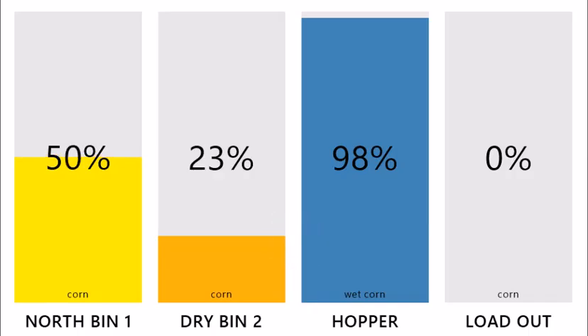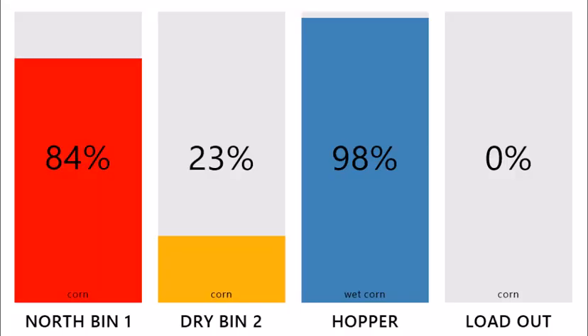I have a sensor here on a bench setup, and I'm going to demonstrate how changing the levels will trigger and reset our alarms. Recall that our high alarm is set to 80%. When my sensor detects that the bin is 80% full, the fill bar begins to blink red. If I continue to fill the bin, my alarm is going to stay active.